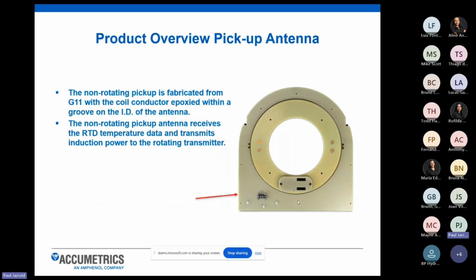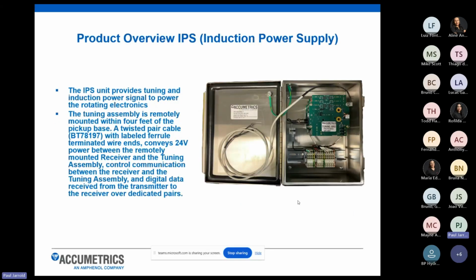We don't have to dwell too much on this, but I touched on it in the last slide. This is just showing you, again, the stationary pickup antenna connection. And then this is our induction power supply unit. So this would be tuned specifically to each customer's application. We will do all the tuning in-house here in our lab, and try and simulate real world environments. So we'll put the transmitter collar on a simulated shaft. We'll put metal in close proximity to the transmitter and pickup antenna to try to do a real world example of what the customer's motor may look like.